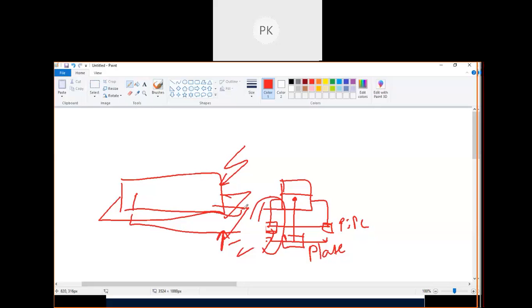Your neutral is connected here. Your neutral conductor is running. You have a trench here, and a cable coming from here to here. That cable has an armor, so the lightning strike's rise in potential will travel through it electrically. But if the armor is connected at both ends, it will be at the same potential.